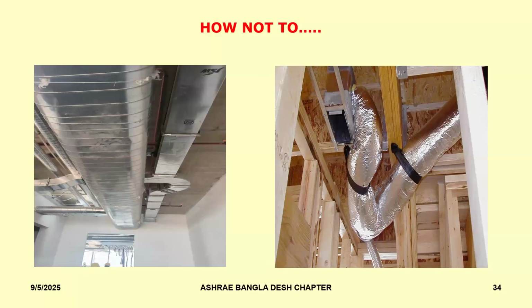When you do ducts, there are some things that you want to be careful about. How you route the ducts, for example. Look at this particular plenum here, which is being fed by this duct. When you run a duct like this, obviously the amount of air that's going to exit this plenum is going to be severely throttled, because of the way the air is flowing. When somebody is designing the system and installing it, the installer probably doesn't realize that doing this is going to impact the airflow. So obviously, when the airflow is impacted, the actual air distribution effectiveness in the space is going to reduce. Therefore, if you started off with a certain outdoor air quantity, that would be inadequate.